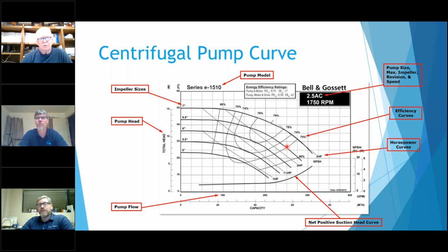But if you all of a sudden need to operate out at this end, now you need 10, or maybe almost 15. So you could need a lot for this pump to work. If you're not going to have enough suction pressure for this pump, you might want to pick another one where you're operating back over here, where the suction requirement is a little bit less.